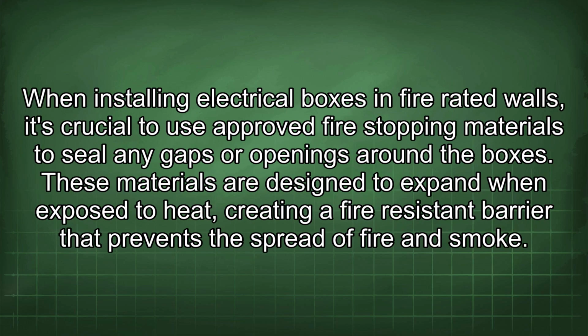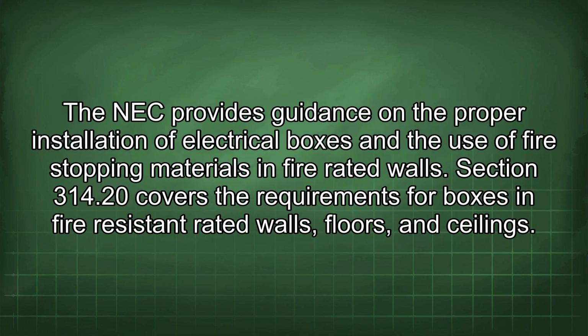When installing electrical boxes in fire-rated walls, it's crucial to use approved fire-stopping materials to seal any gaps or openings around the boxes. These materials are designed to expand when exposed to heat, creating a fire-resistant barrier that prevents the spread of fire and smoke. The NEC provides guidance on the proper installation of electrical boxes and the use of fire-stopping materials in fire-rated walls.